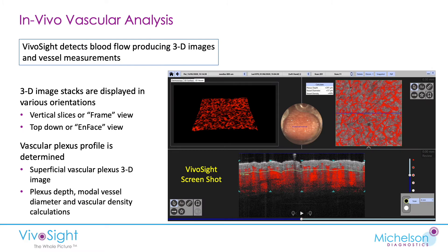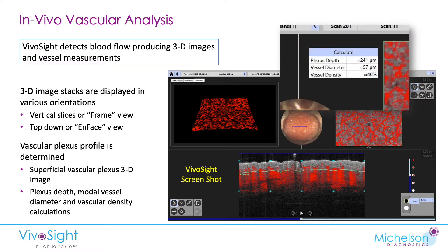VivoSight OCT also has a capability to image blood vessels. This is an actual screenshot of the machine display after capturing an image of some tissue that has had a patch removed and shows some erythema. We can see a map of all the vessels, and importantly we can get measurements of the depth of the active plexus — in this case 241 microns, just under a quarter millimeter down. The most common vessel diameter is 57 microns, and the density is 40%, so quite a lot of tissue is comprised of active vessels at this depth.